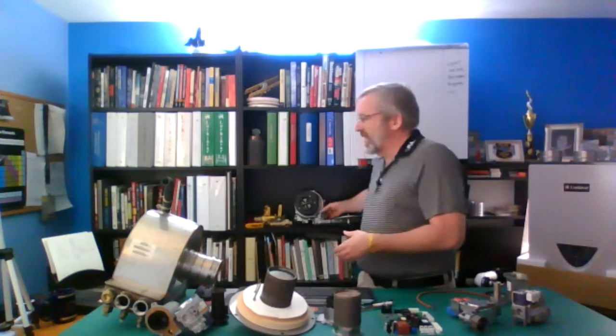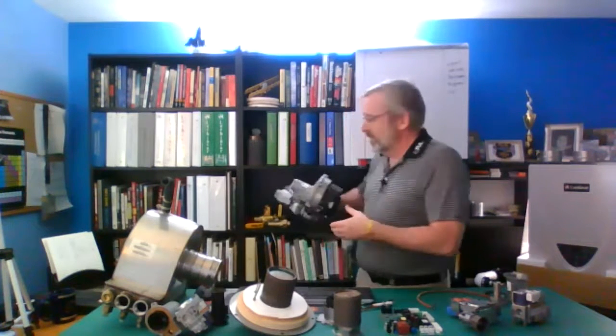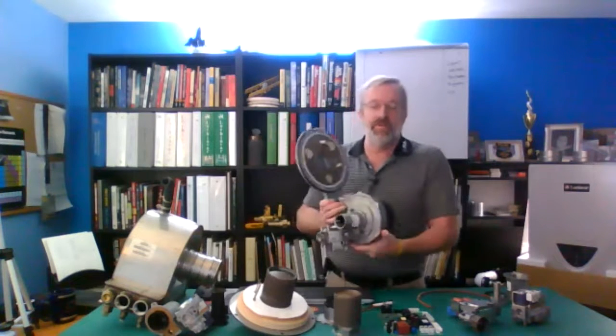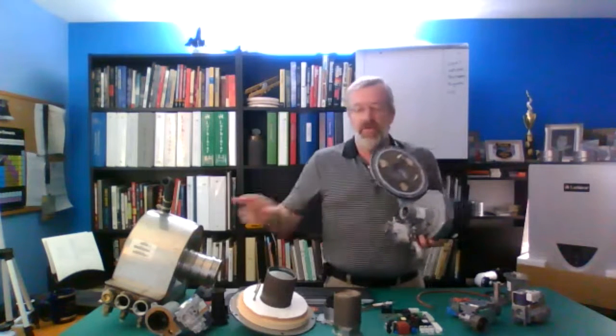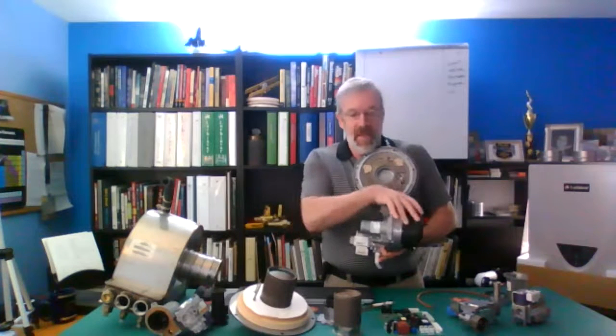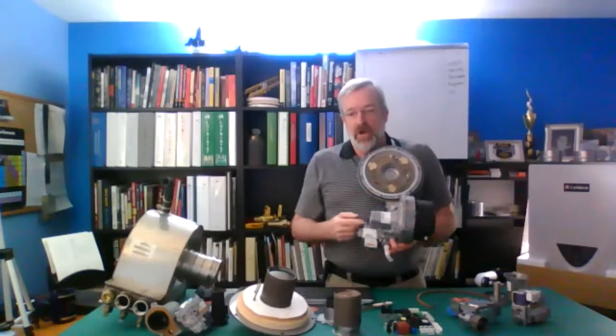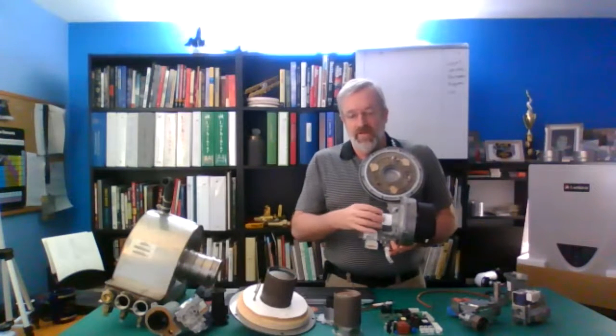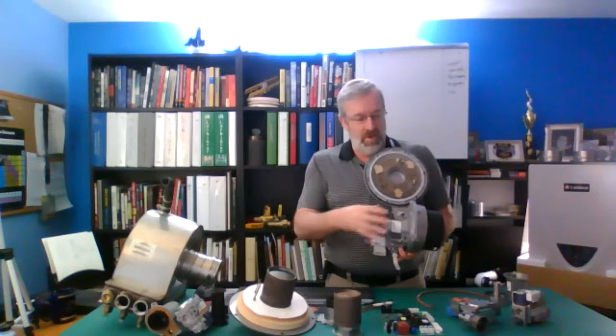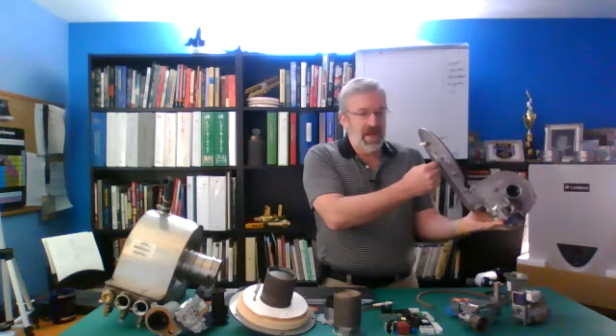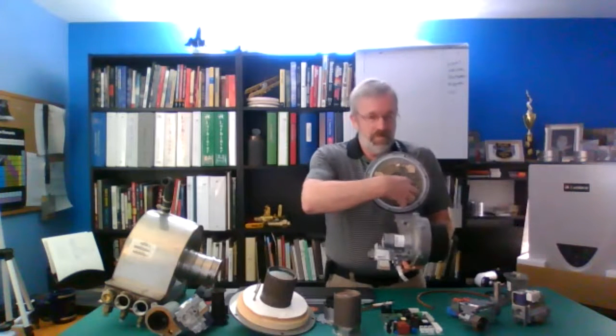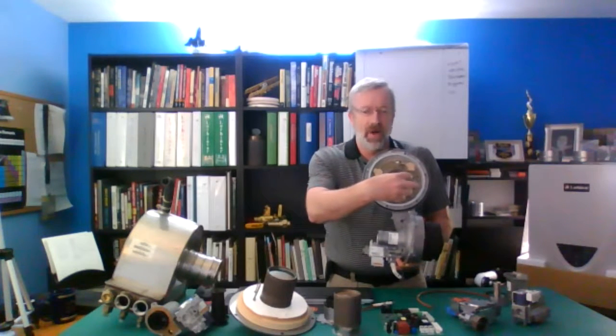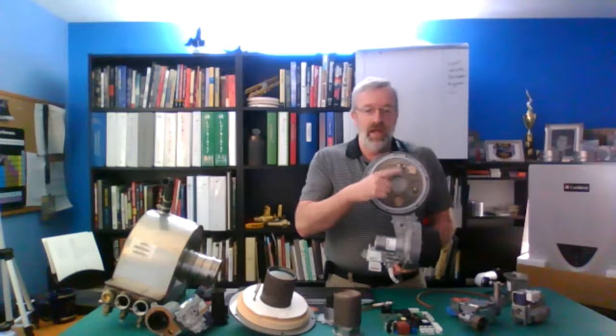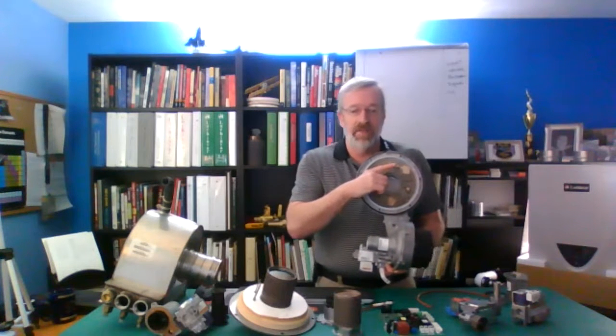As it moves across that venturi, and here's a complete assembly for a 5-to-1 turn down, this is actually off this water tube style boiler, this fan draws the air through this venturi. The venturi pulls the gas through. As we mix down in here, we're going to push it down through the air arm. That air arm is going to put it through the burner. We're going to spark, and then we're going to test and sense the flame right here.